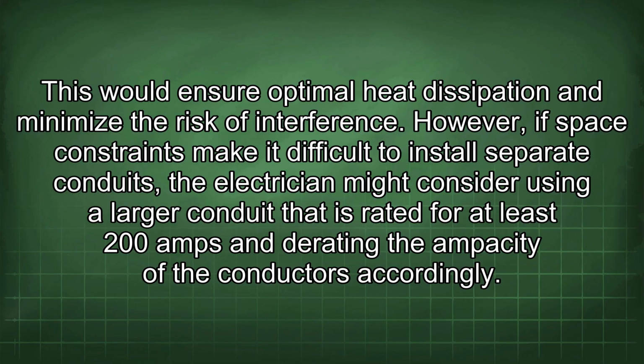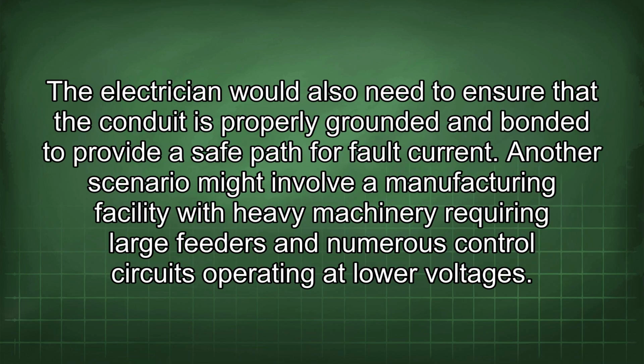However, if space constraints make it difficult to install separate conduits, the electrician might consider using a larger conduit that is rated for at least 200 amps and derating the ampacity of the conductors accordingly. The electrician would also need to ensure that the conduit is properly grounded and bonded to provide a safe path for fault current.